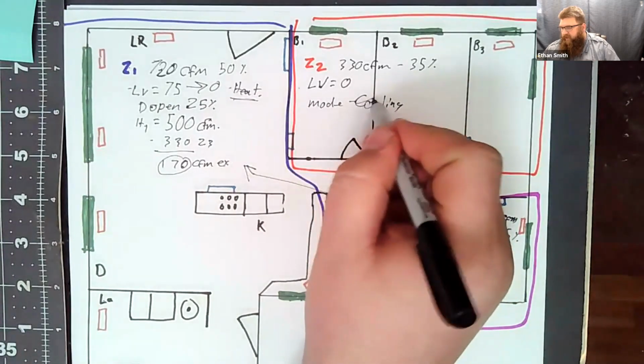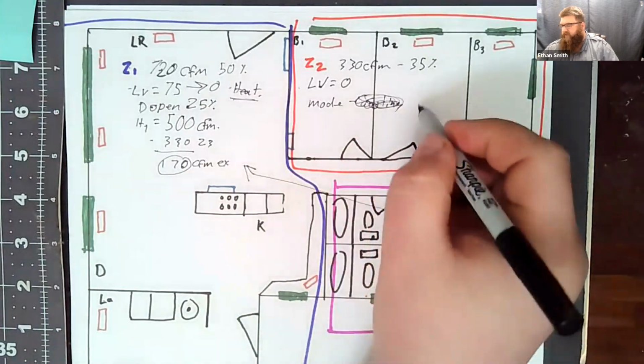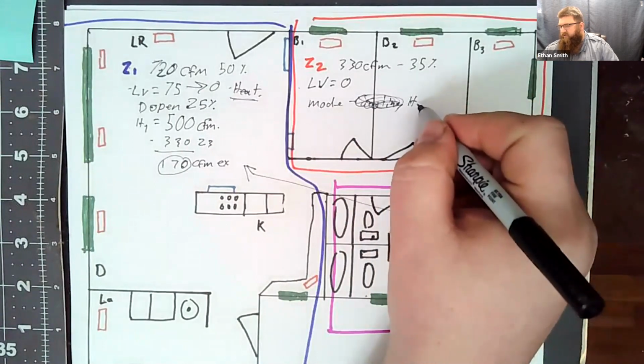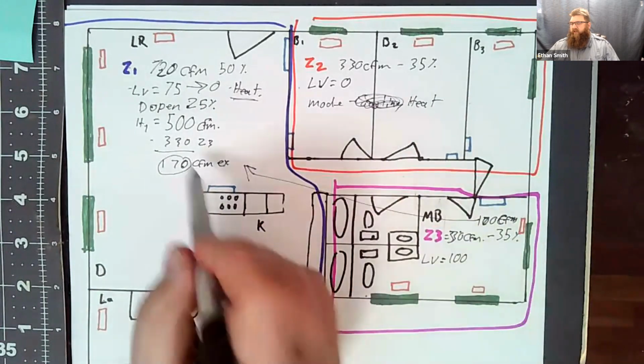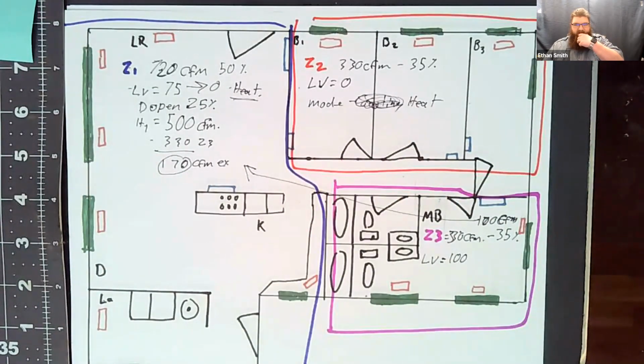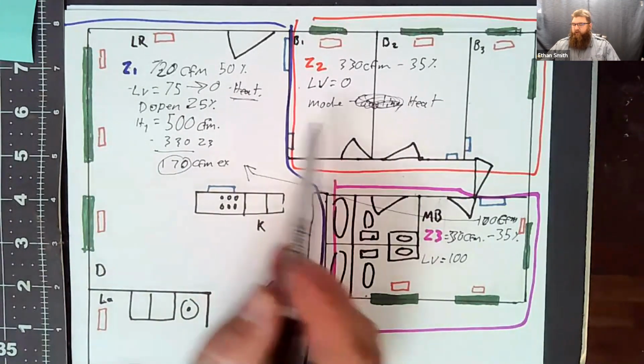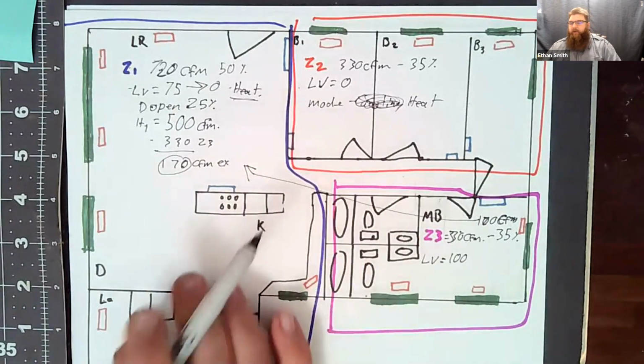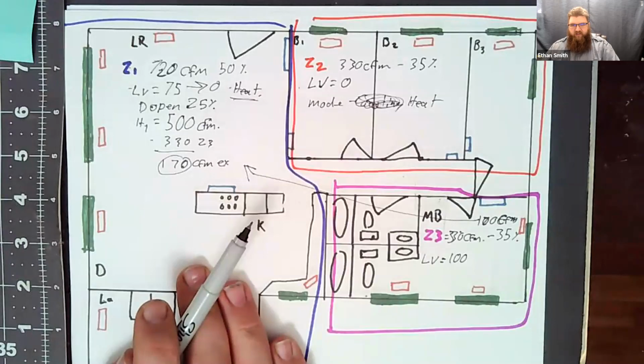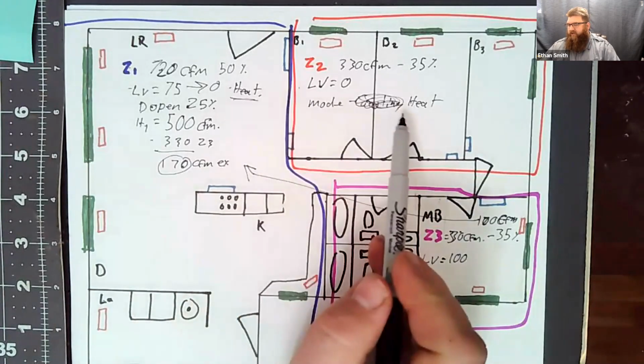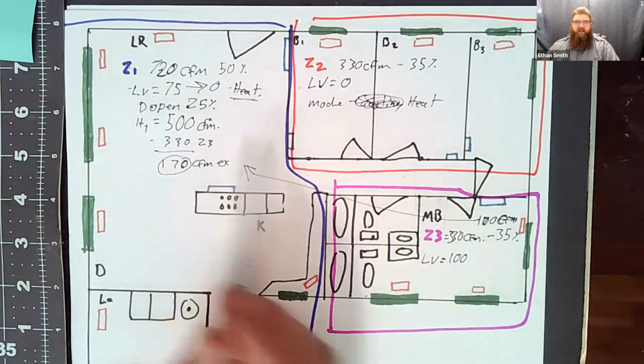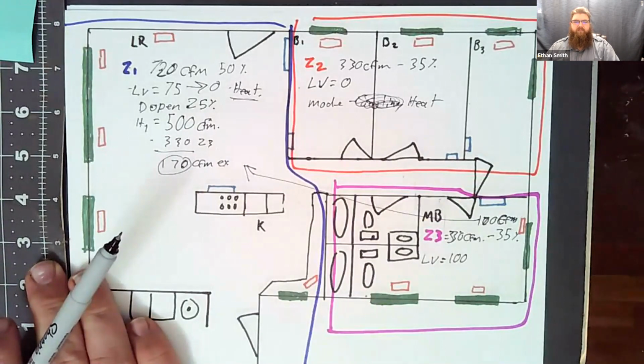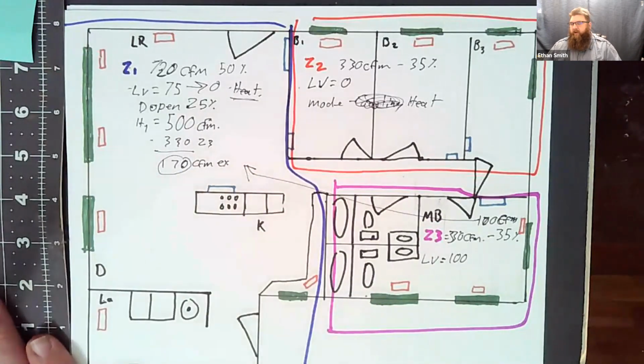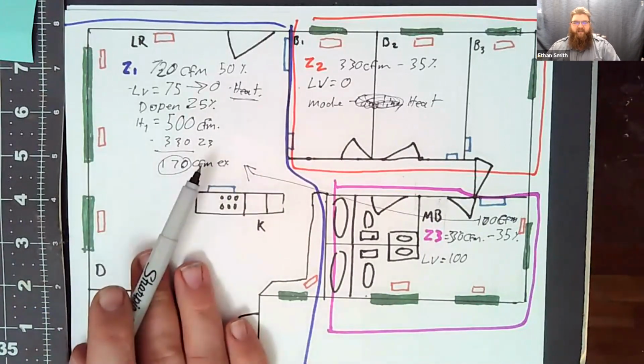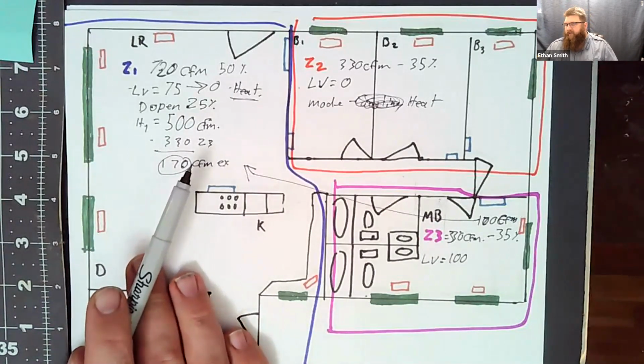Now, if my mode in zone 2 were in heat, it would actually split that 170 CFM between both zone 1 and zone 2. So it would start to relieve into both of these zones. Okay. If we still had an excess air problem after opening both of these zones to 100%, and I know it doesn't work out in this example, but say I had this little tiny zone that was calling for heat and I had a single stage piece of equipment. It's got a crap load of air to get rid of. If it gets all the zones that are in the heating mode opened up all the way, it will then go out and start to relieve into zones that are in a cooling mode or off at that point. So that's kind of the last ditch effort. If we ever get to that point in our zoning system design, we've done something terribly wrong. Okay. But this is just kind of an example of how that intelligent relief works.